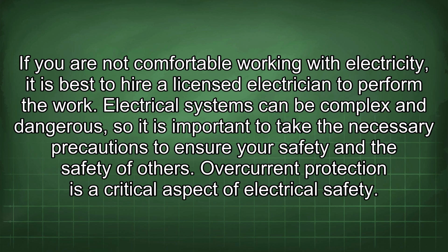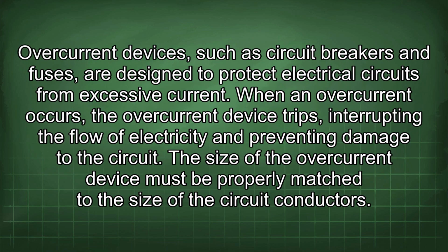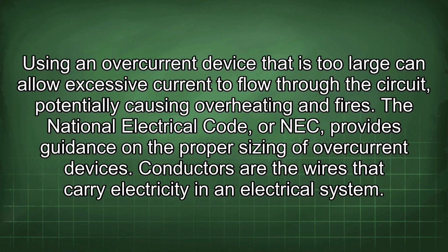Overcurrent protection is a critical aspect of electrical safety. Overcurrent devices, such as circuit breakers and fuses, are designed to protect electrical circuits from excessive current. When an overcurrent occurs, the overcurrent device trips, interrupting the flow of electricity and preventing damage to the circuit. The size of the overcurrent device must be properly matched to the size of the circuit conductors. Using an overcurrent device that is too large can allow excessive current to flow through the circuit, potentially causing overheating and fires. The National Electrical Code, or NEC, provides guidance on the proper sizing of overcurrent devices.